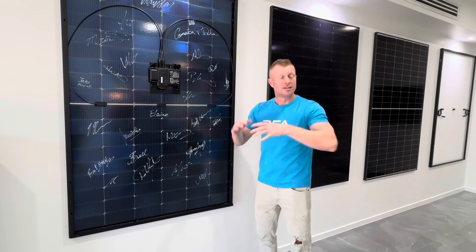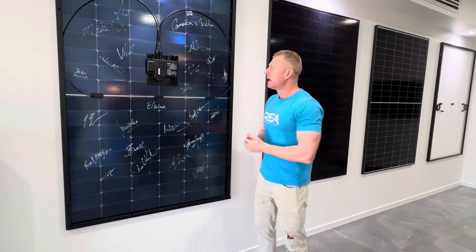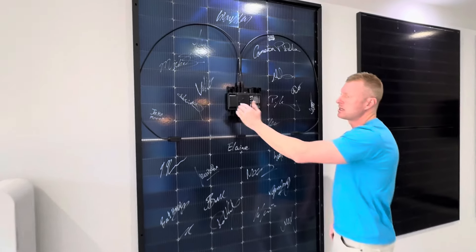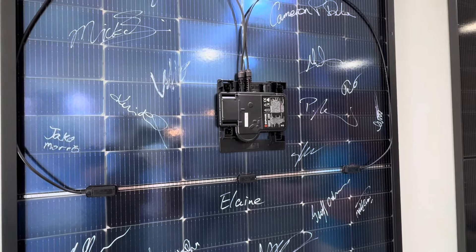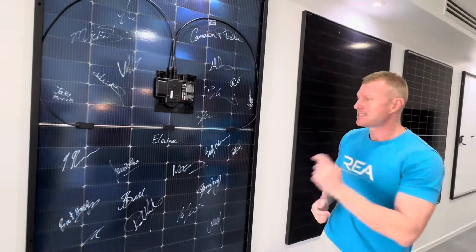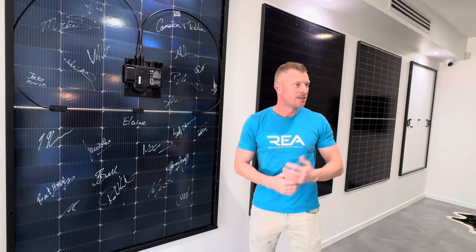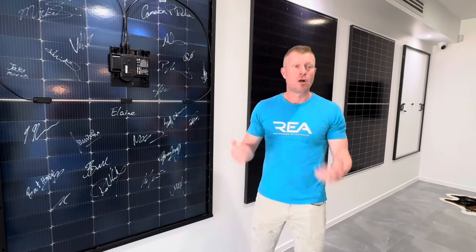During the day, when we have low-angle light or cloud cover, we have capacitors in here which hold a charge to keep the MPPT tracker on and ride over those periods — so we're not constantly turning off and on. We squeeze more energy out of it. It doesn't sound like a lot, but 2 to 3% improvement daily, and 10 to 15% overall performance every single day for 25 years means we generate a lot more energy.